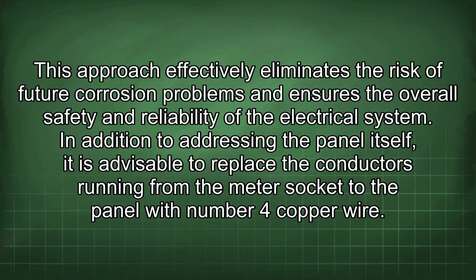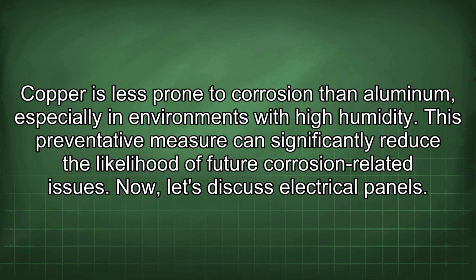In addition to addressing the panel itself, it is advisable to replace the conductors running from the meter socket to the panel with number 4 copper wire. Copper is less prone to corrosion than aluminum, especially in environments with high humidity. This preventative measure can significantly reduce the likelihood of future corrosion-related issues.